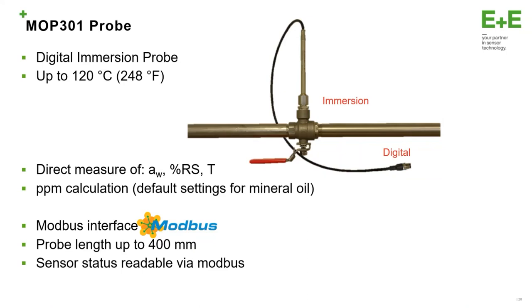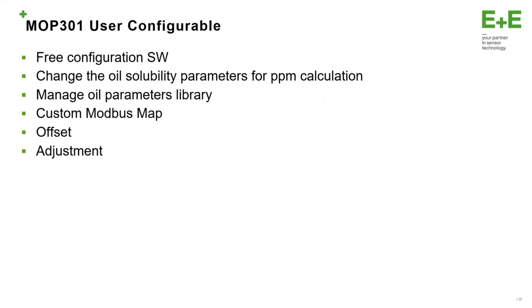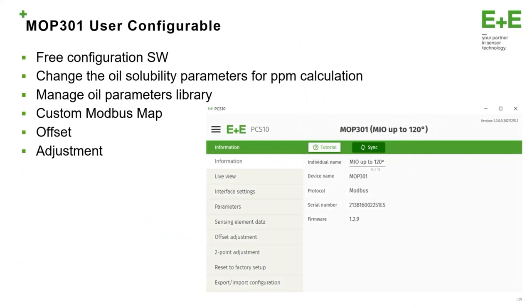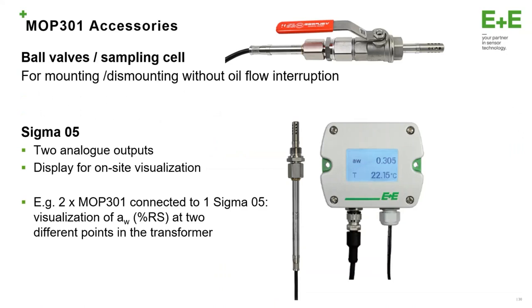Another feature is the free configuration software — the user can change the solubility parameters for the PPM calculation. It means if the oil is a mineral oil, you can change the solubility parameters and have PPM calculation for other oil types. In addition, the user can manage an oil parameters library, build a custom Modbus map, so with one request you can get all the parameters. It's also possible to adjust and perform an offset.